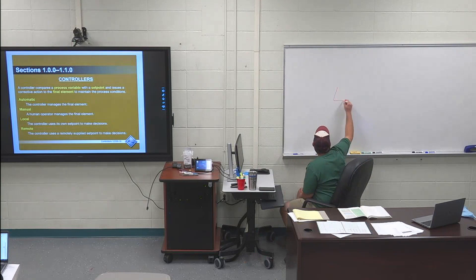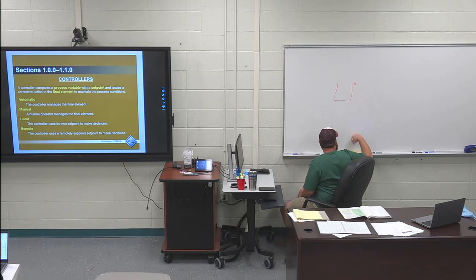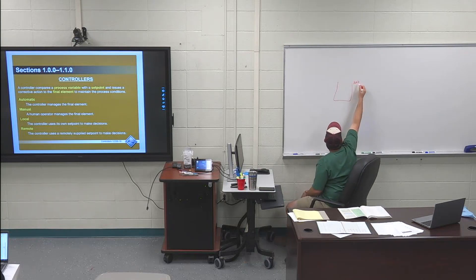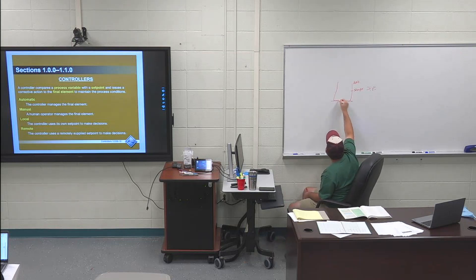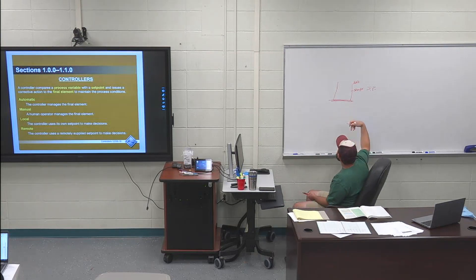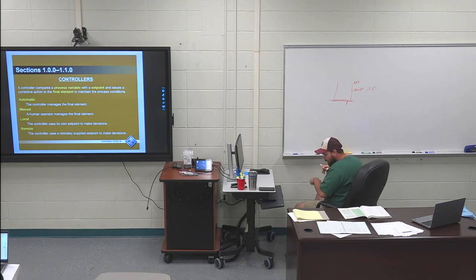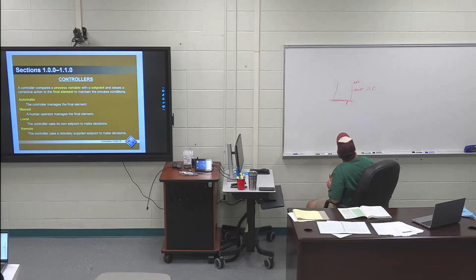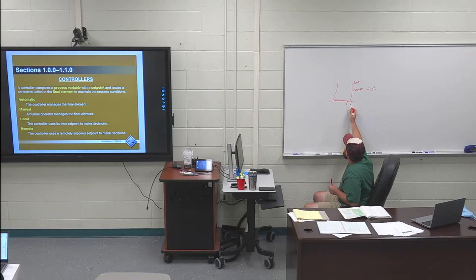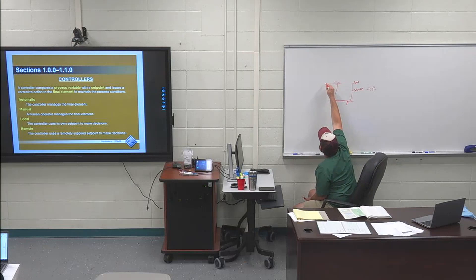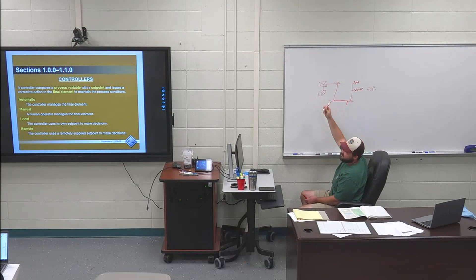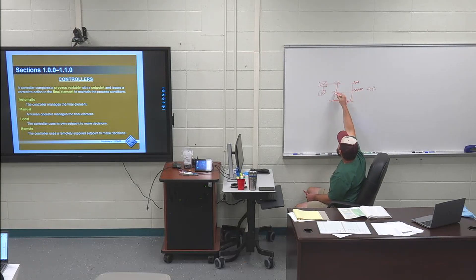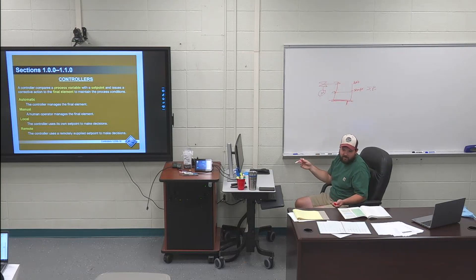Same thing as I always say — if I had a hundred-foot tank, our set point is 50 feet, and the tank is empty at zero. Whatever you're using to measure level — whether that's an ultrasonic, a differential pressure cell, or a pressure transducer — if you have zero feet in the tank, it's going to send maybe a hundred percent open to the motor-operated valve to start filling. But if I was at 47 feet, it's only going to open the valve about 5% because it's almost there.